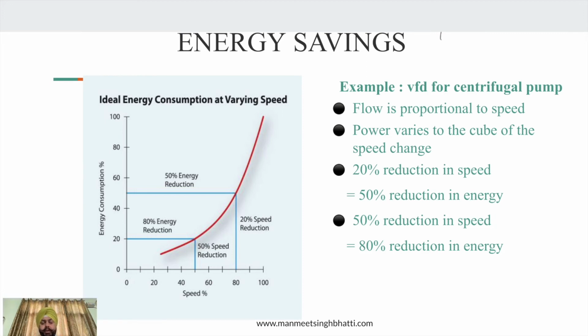The VFD will automatically control the speed and delivery of your product from the pump directly to the farthest point at 7 bar. So it will not bother about what speed it is running at, or what the motor behavior is. It will make sure that you get 7 bar at the farthest point. It is one of the biggest things for a pump. So it becomes a closed loop for you. And how does the energy saving come?